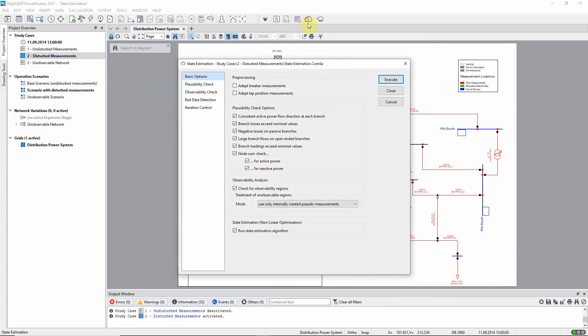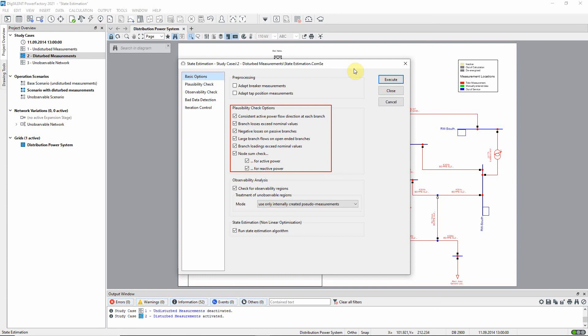This is where the plausibility check becomes useful as it provides a means of discovering measurements which are clearly erroneous. Such implausible measurements will be ignored for the purposes of the actual state estimation calculation.